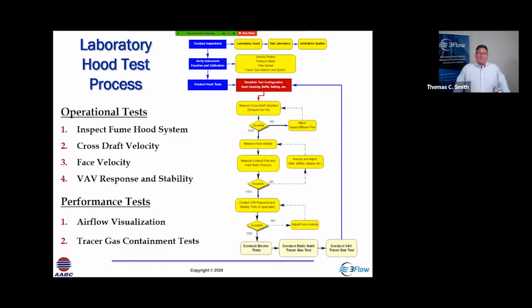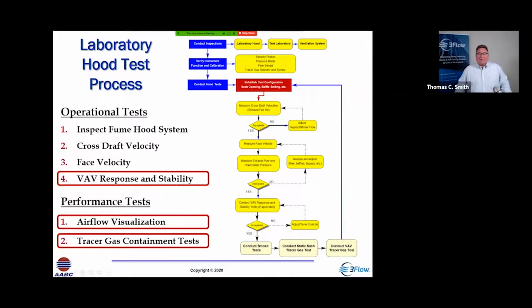So we have a process, and this was developed with the US EPA to put it into a standard operating procedure. It's based on ASHRAE 110, but we start with inspection of the hood, cross draft velocity measurement, face velocity, VAV response, then our performance test. For this presentation, I'm going to focus on VAV response, the airflow visualization, and tracer gas containment, because I think everyone here listening and watching knows how to do the cross draft and velocity tests very, very well.